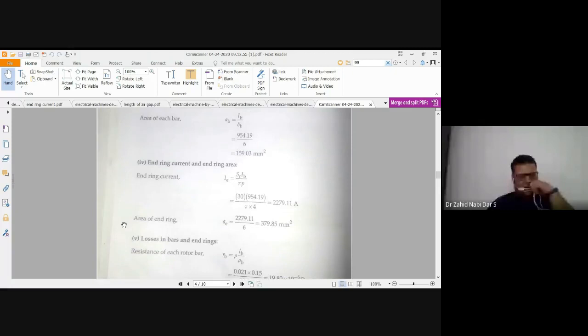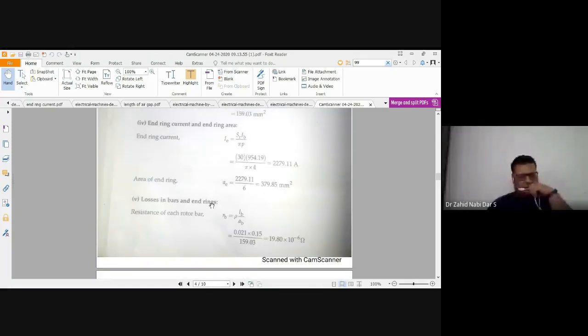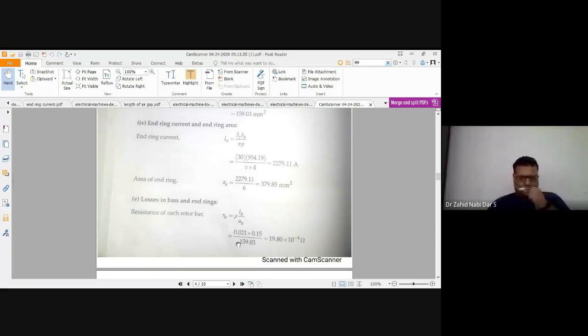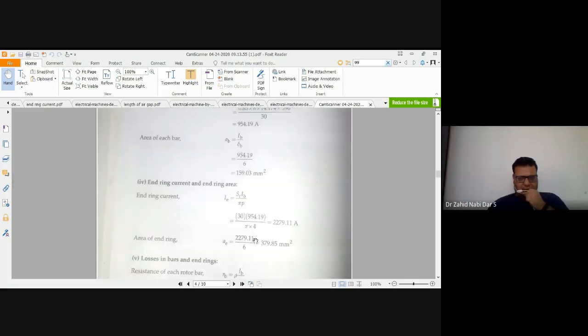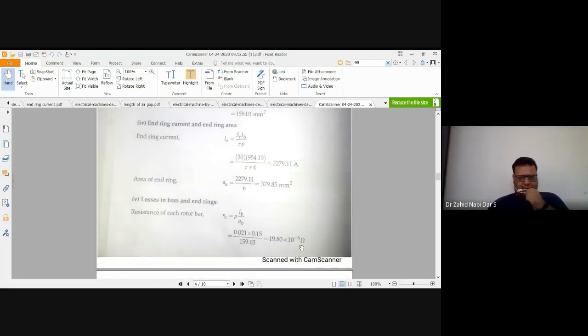So how to calculate the value of R? For losses in bars and end rings, first of all we have to go for the resistance. Resistance of each rotor bar would be equal to rho L by A. Please switch off your mics. The rho value is 0.021, LB value was 15 centimeters, so 0.15, and the AB value you calculated is 159.03. So from here you get a resistance of 19.80 times 10 power minus 6 ohms.